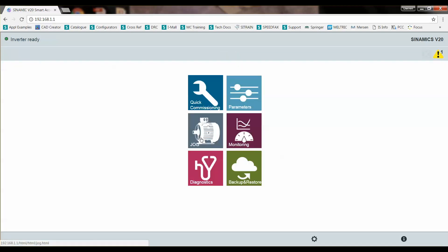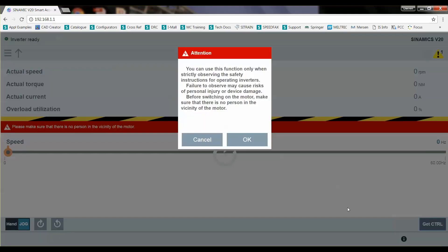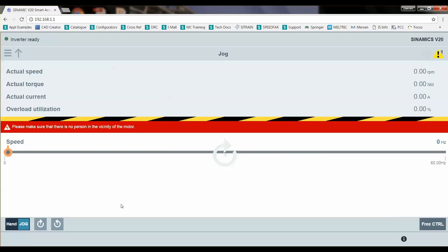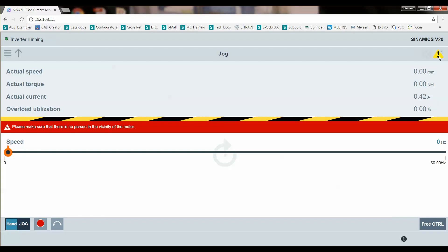So we'll go to the jog and be able to control our drive and turn it on for the first time. So we'll get control of the drive. We want to do that motor identification routine. So I'm going to be able to turn it on and keep it on. So turn it into hand mode and turn the drive on. You can see it's sending out some current, but no speed doing this identification routine. Once we're done with the routine, the current will go to zero and this alarm will go away. And then we can run our drive if we like. It takes a minute or so, depending on the size of the drive and motor.